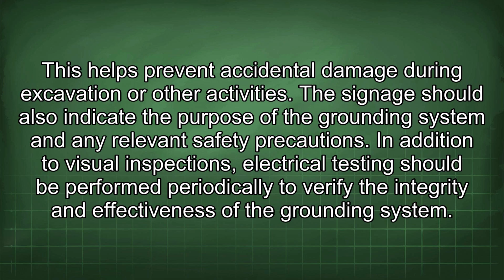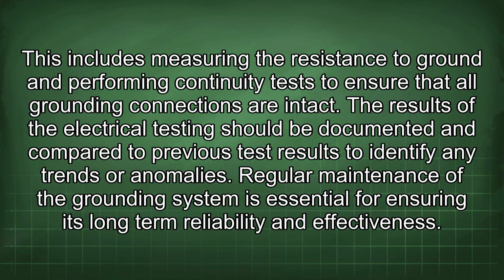In addition to visual inspections, electrical testing should be performed periodically to verify the integrity and effectiveness of the grounding system. This includes measuring the resistance to ground and performing continuity tests to ensure that all grounding connections are intact. The results of the electrical testing should be documented and compared to previous test results to identify any trends or anomalies. Regular maintenance of the grounding system is essential for ensuring its long-term reliability and effectiveness.